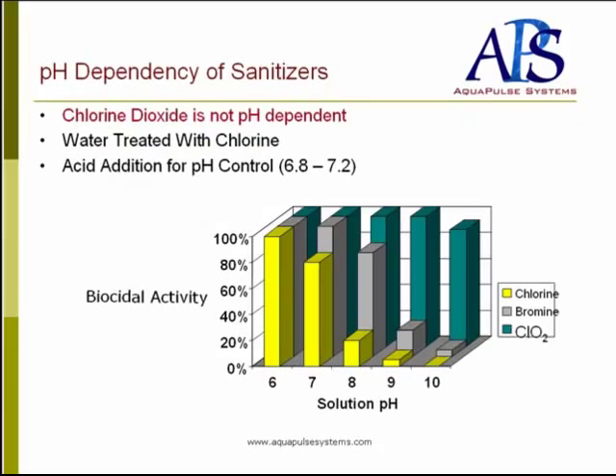Chlorine dioxide is not pH dependent. As the chart shows, water treated with chlorine requires acid addition for pH control between 6.8 and 7.2, which are the effective ranges for chlorine. You can see that chlorine dioxide is effective from pH 6 to pH 10 without any acid addition or pH control.